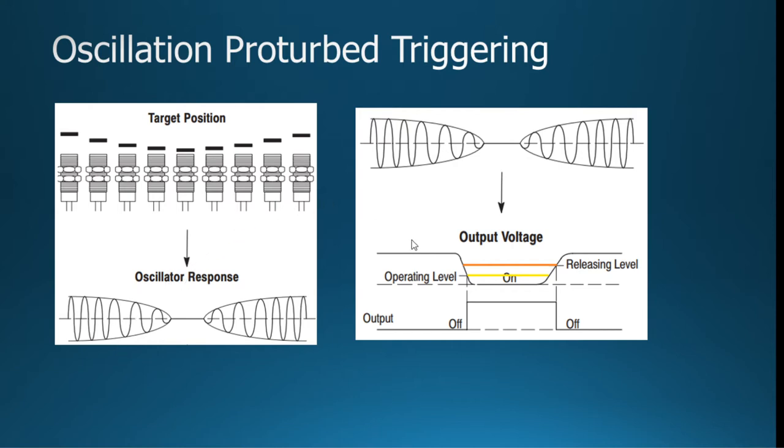On the right hand side, what that's showing there is that there is kind of a margin of area there between the yellow and the orange, just like we kind of seen in the optical sensors. There's kind of a holding and then there's a release. So what happens is something comes in, it'll trigger it, but actually may stay in there a little longer as it starts to leave. So maybe it got triggered at three, but maybe stay open until about four. And so there's a 10% hysteresis, which means three millimeters plus 10% would be 3.3 millimeters.